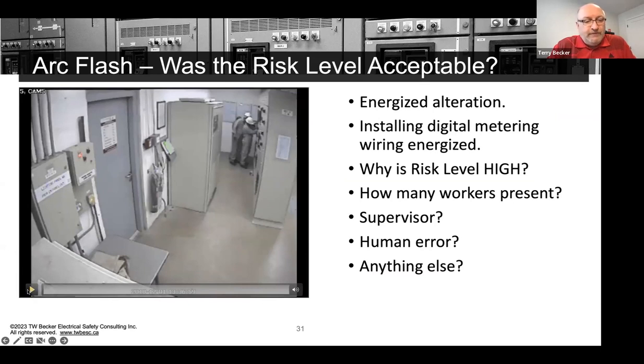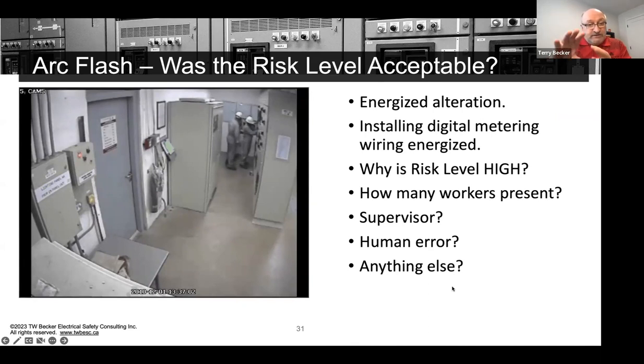So I'll play the video, right? It's a lower incident energy arc flash, because you'll see from that MCC starter bucket, you'll see a smaller sort of plasma ball come out and molten metal, and it goes away quickly because a protective device is clearing it. So that's why arc flash will be fast, because we expect that the upstream electrical protective device will clear quickly if it's a branch circuit, slightly delayed if it's a main breaker that would see it. But if it's a branch circuit, it'll clear very quick.